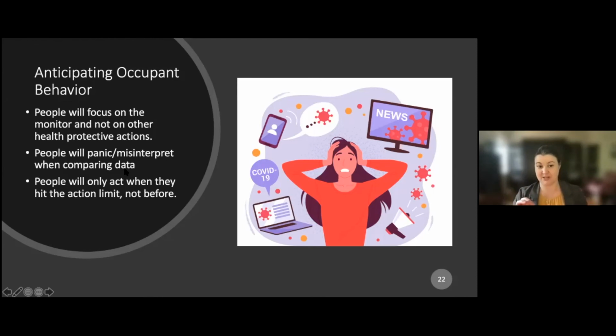So this point is actually probably my biggest concern: if you set an action limit and tell people they've got to stay under 1000 ppm, people will only act when they hit the action limit, not before. What we actually want is for people to regulate as close to ambient as possible, keeping CO2 levels down by having their windows open as much as possible, depending on HVAC setup and other factors. If you set a relatively high action limit like 1000 ppm, people being people will try to do the minimum and just stay under that limit, which isn't the point.